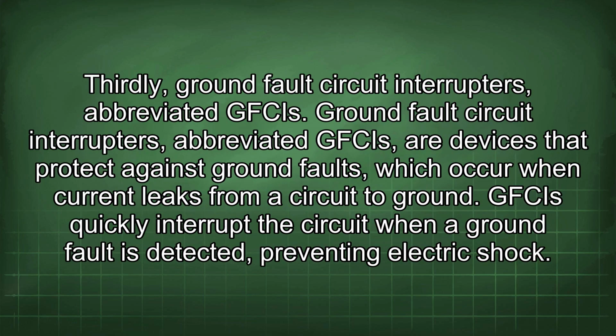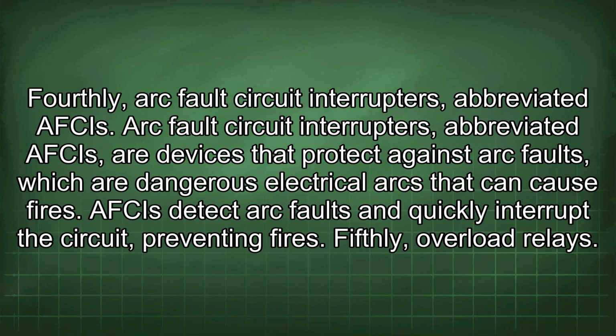Thirdly, ground fault circuit interrupters, abbreviated GFCIs. GFCIs are devices that protect against ground faults, which occur when current leaks from a circuit to ground. GFCIs quickly interrupt the circuit when a ground fault is detected, preventing an electric shock. Fourthly, arc fault circuit interrupters, abbreviated AFCIs. AFCIs are devices that protect against arc faults, which are dangerous electrical arcs that can cause fires. AFCIs detect arc faults and quickly interrupt the circuit, preventing fires.